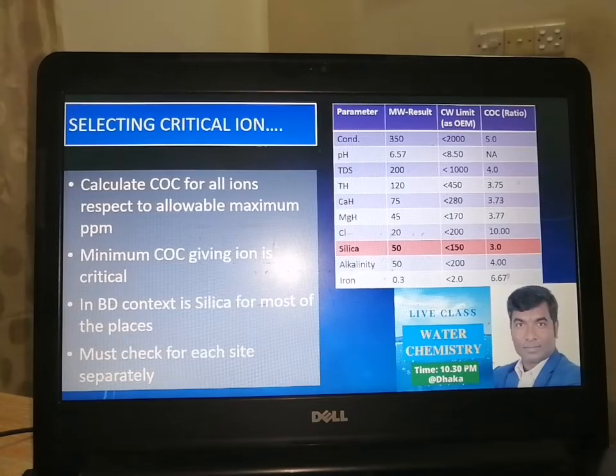The critical ion is the ion which gives the lowest cycle of concentration for a particular system, for a particular makeup water or particular site condition. Once we understand the critical ion, we can understand the design: what kind of pretreatment plant I have to design, what cycle of concentration I have to consider, and based on that I can calculate the blowdown and the makeup. Accordingly I can design the pretreatment, the tank size, and many other things. So before going to the plant design, I must do the critical ion selection for any project.